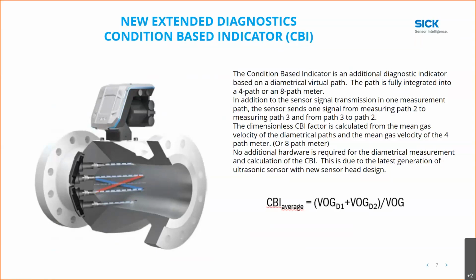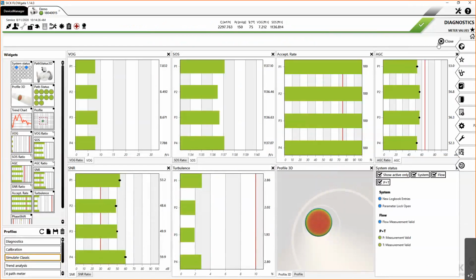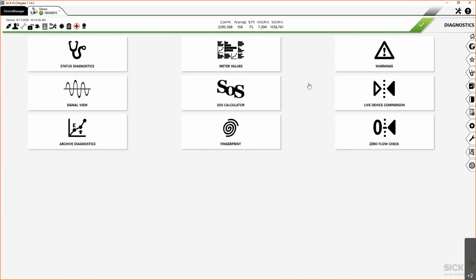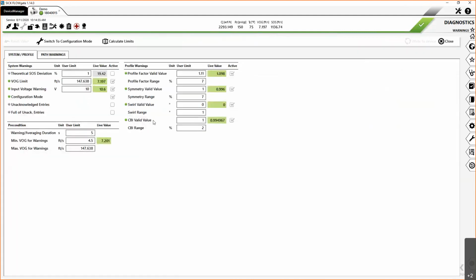So the CBI factor is a calculated value. As you see in the formula at the bottom, we're comparing the 4-path average gas velocity to the 1-path using this virtual path, and we can come up with any deviations. As you know, the 1-path has a higher change whenever the flow profile changes compared to the 4-path. So you can take advantage of that inside the software, as we see here. I'll close this out, and if we go to our warnings page, you can see where your CBI value is indicated, and you can set up a tolerance so that you can alarm off of that virtual path before maybe the 4-path actually gives you an alarm by doing that comparison.